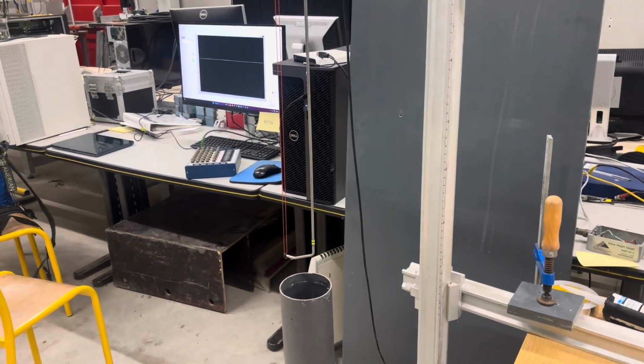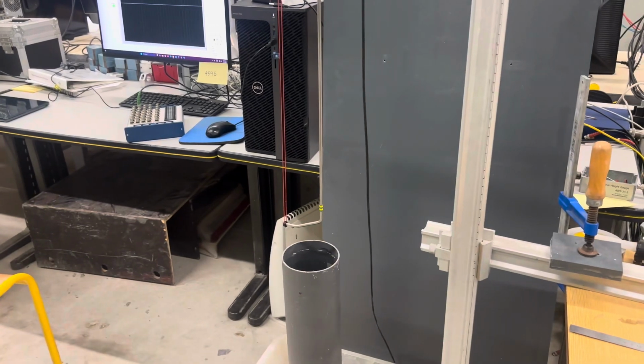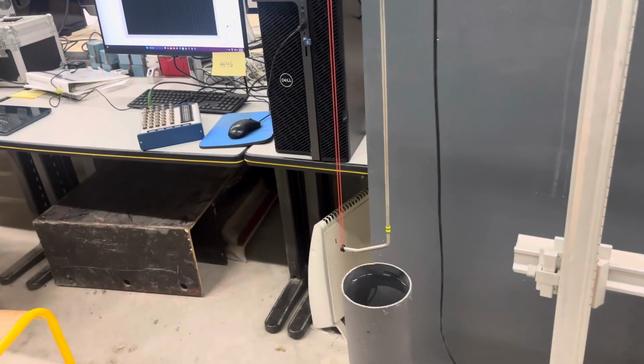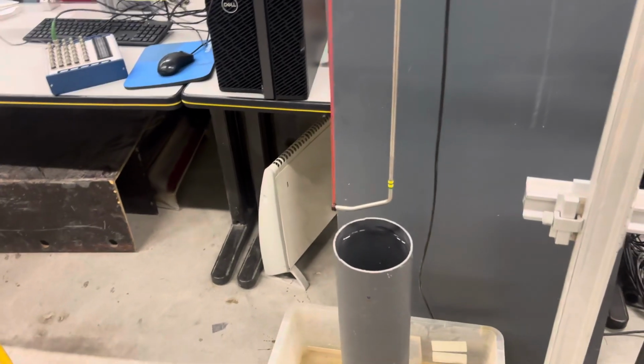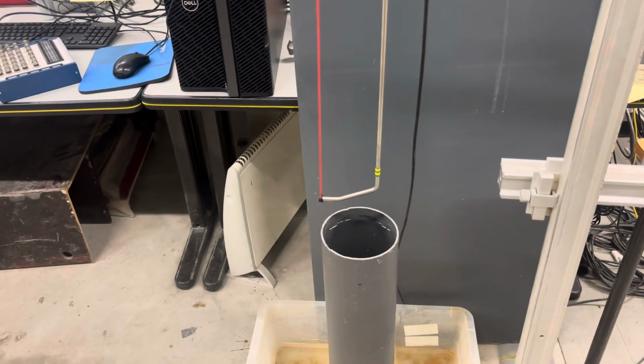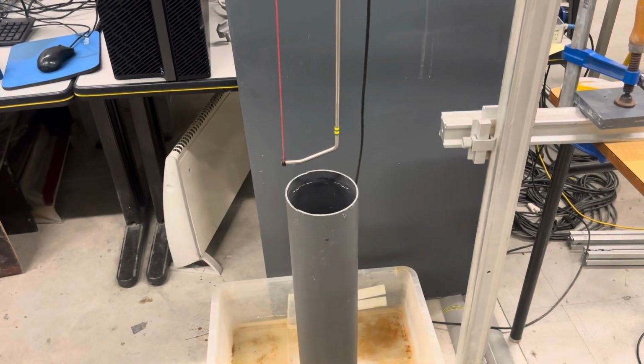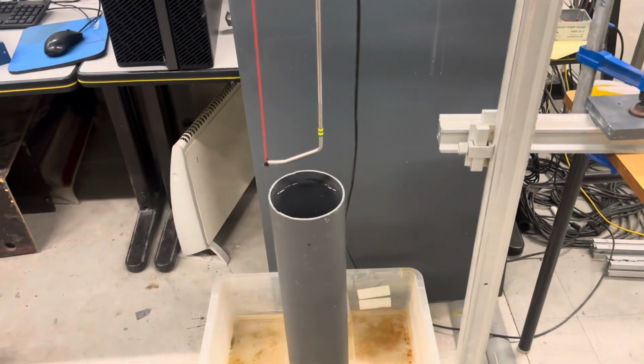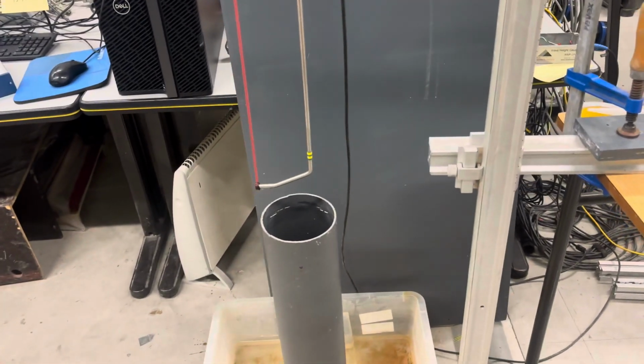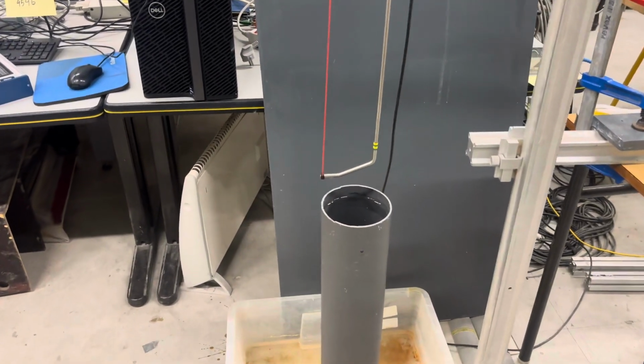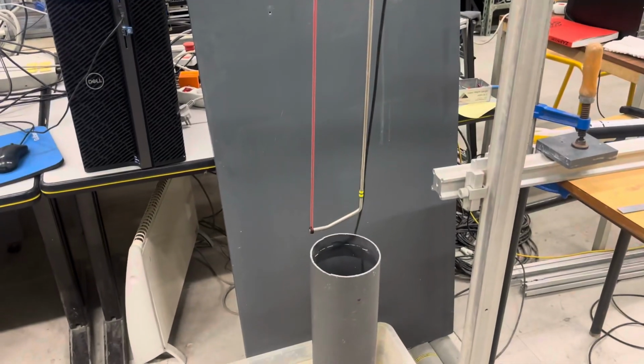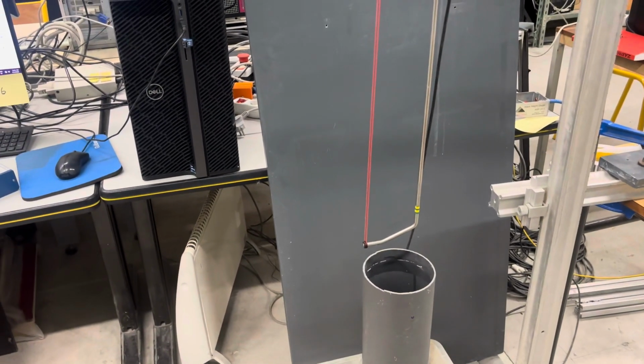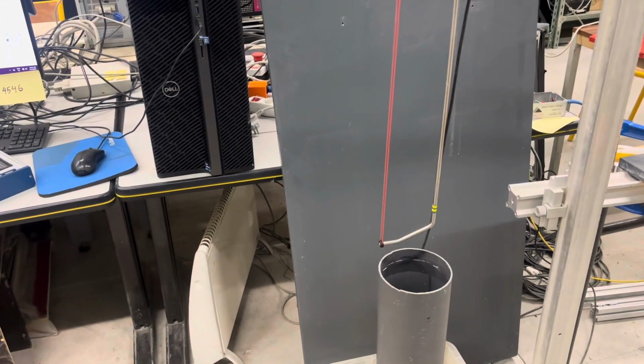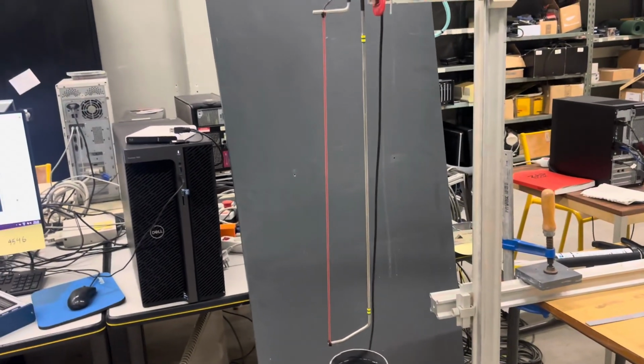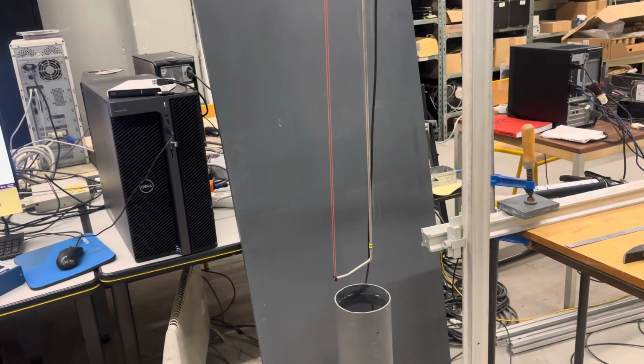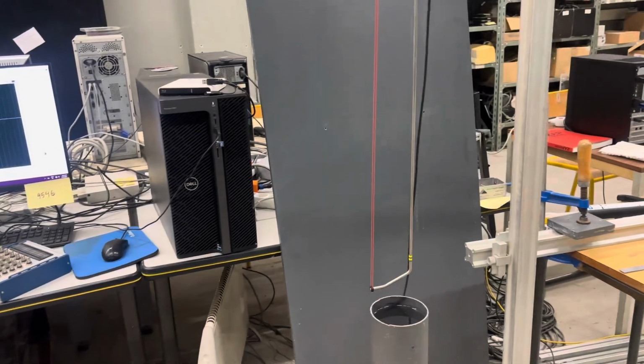So we will start with the wave gauge probe, which can be submerged or placed near the water surface in a wave tank or flume. In our case, we are using a cylindrical container filled with water. Our student used this setup to calibrate the sensor. This probe, or the sensor, senses water surface elevation and converts it into a corresponding analog voltage signal, usually in the range of 0 to 5 volts, depending on the calibration and water height.